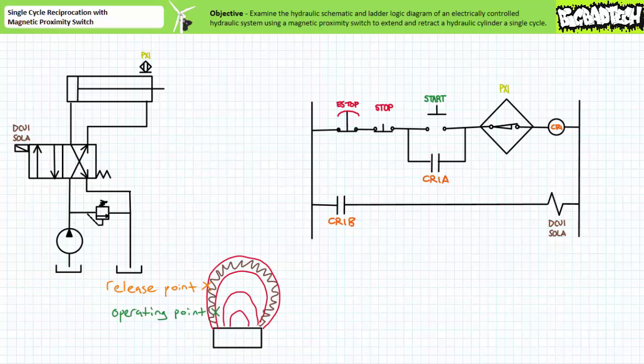Note the overlap between these two regions in physical space. This is known as hysteresis or span, very similar in nature to that exhibited by a pressure switch which activates at a certain set level when pressure is rising and deactivates at another smaller reset level when pressure is falling. This region is desirable because it prevents switch chatter when a magnetic object is hovering just inside the operating point and experiencing physical vibration or electrical noise.